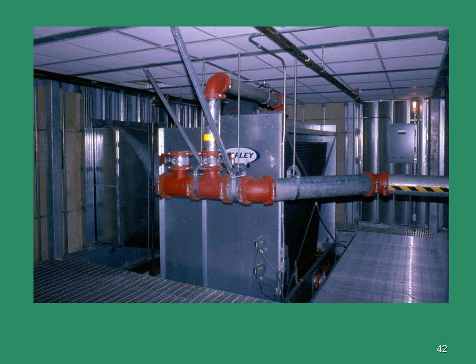What was it before? About 62, 63. At the property line? Most noise ordinances say that at residential properties, thou shalt not exceed 60 decibels during the day and 50 decibels at night. Since this is 24/7 computer equipment, serving all of the corporation, it was a 24/7 facility, so we had to work to the nighttime limits.